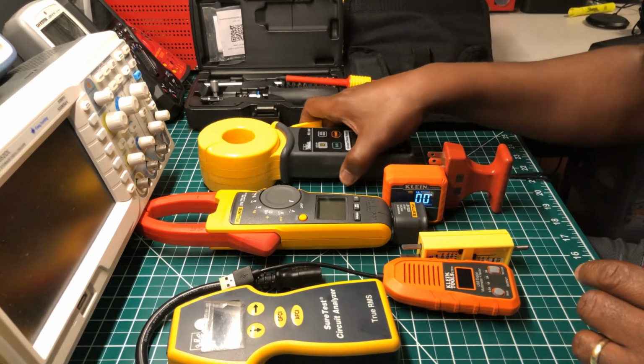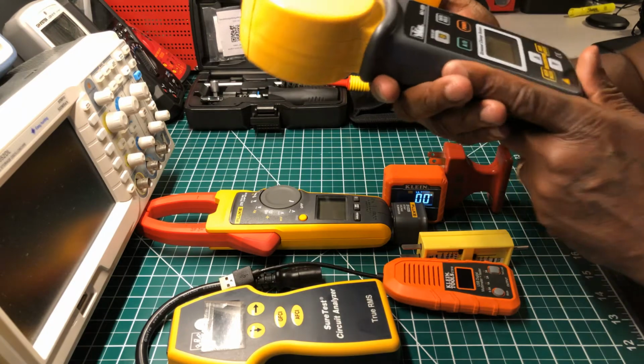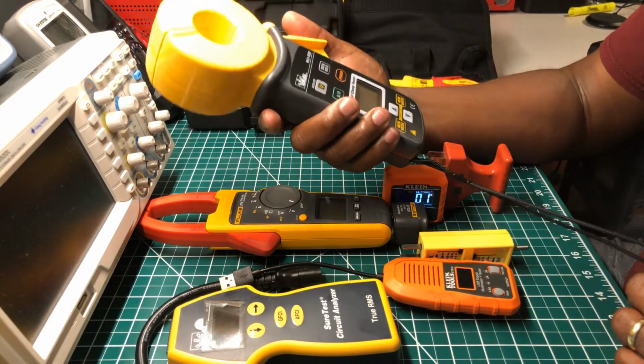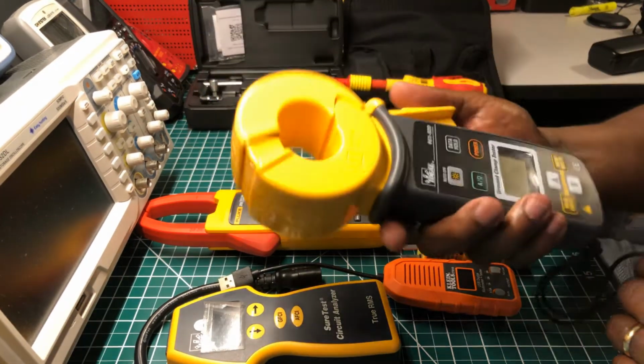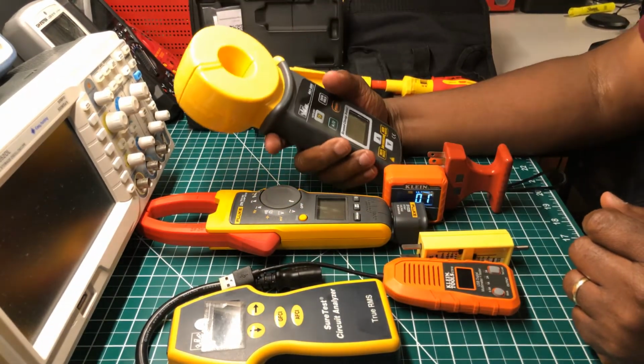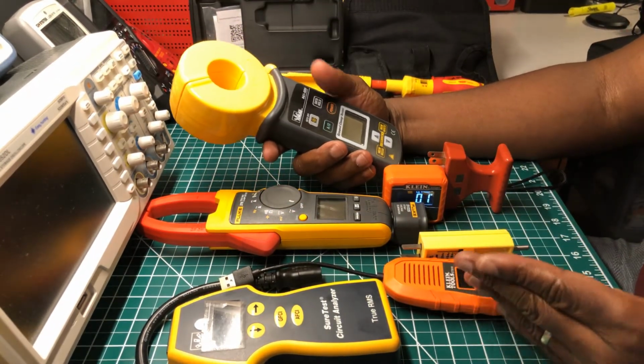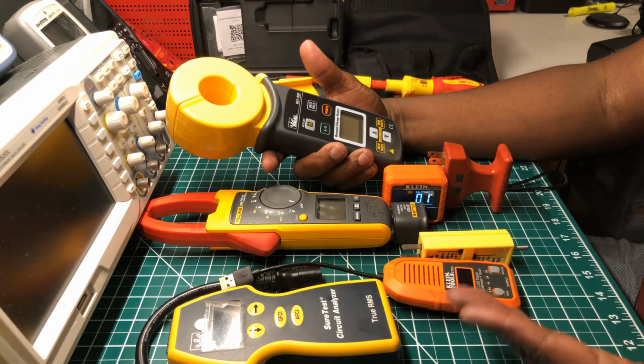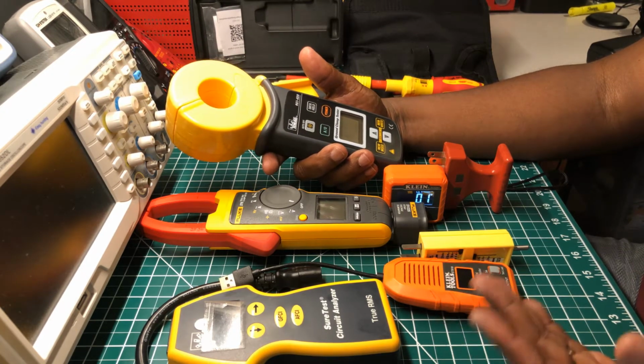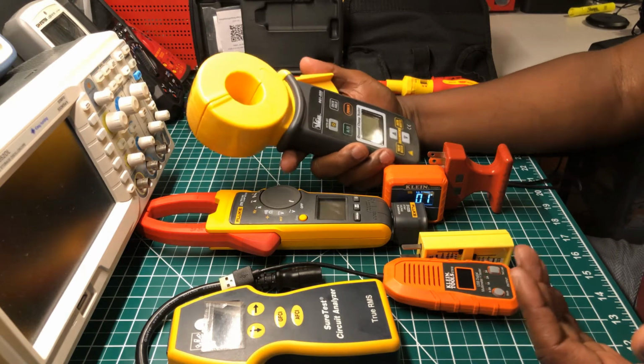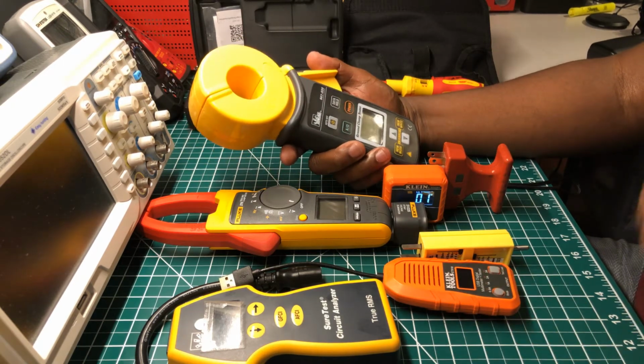Now this right here is a ground clamp resistance tester, the big kahuna right here. After you want to make sure your panel is grounded, the whole system is grounded, when you go out and test that ground rod, you want to make sure it's below 25 ohms. That's code in the NEC.